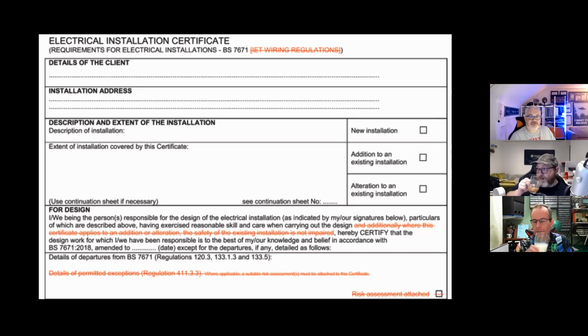Eddie Clements has said, would you put a life support machine on an RCD? No, absolutely not. And people do have dialysis machines and medical systems at home nowadays, so no, this isn't practical. There always must be - if you are the selector, erector and designer, taking all due care and attention to work from the regs and select and erect accordingly, you should be allowed to put in AFDD where you need to, RCD where you need to, and non-RCD where you need to for particular use, and then give said instructions to the user for safe operation. We're having all these decisions taken out of our hands, which is wrong, because it makes it easier for a certain part of our industry to just work to rule of thumb.